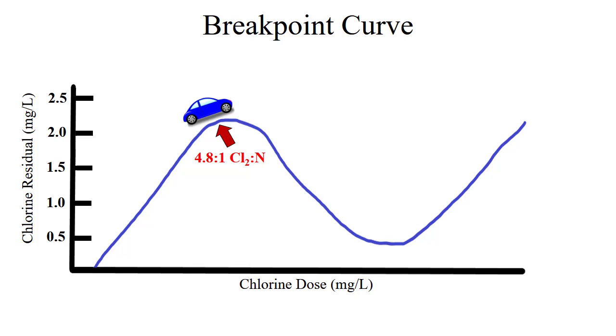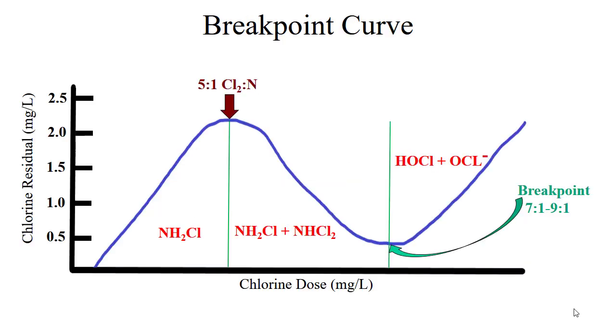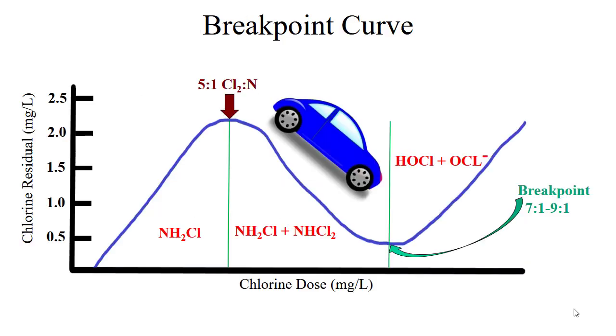In this example, the free ammonia concentration is 0, the free chlorine residual is 0, and we do not have data on the total chlorine residual. We would be anywhere to the right of the 5-to-1 ratio and to the left of breakpoint on the curve. If we had a free chlorine residual, we'd be somewhere to the right of breakpoint in this area on the curve.